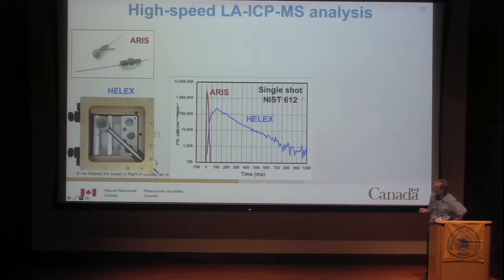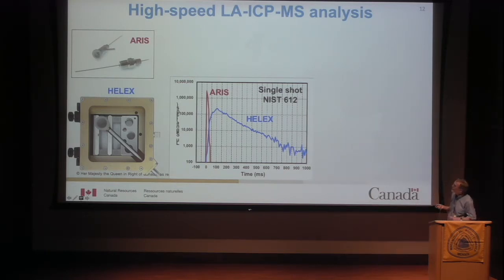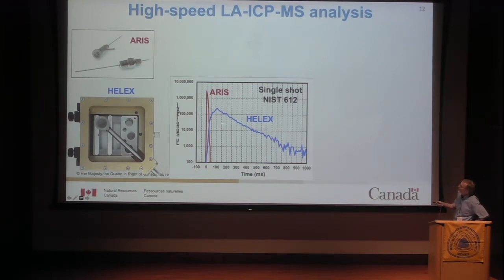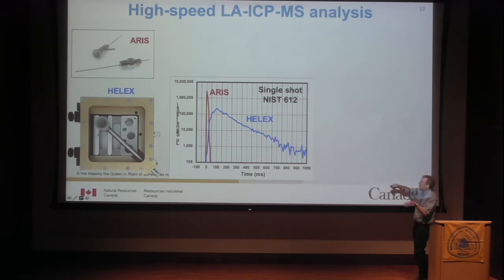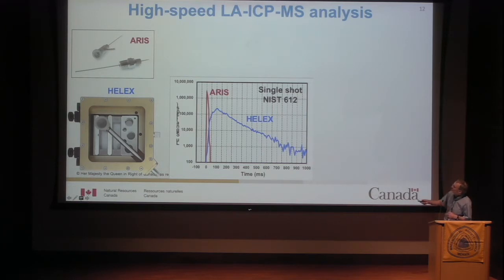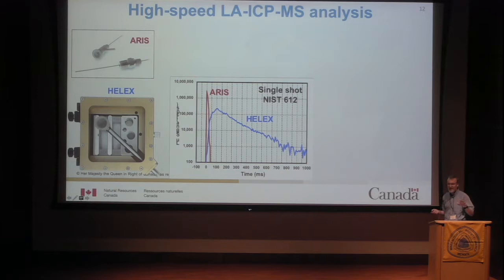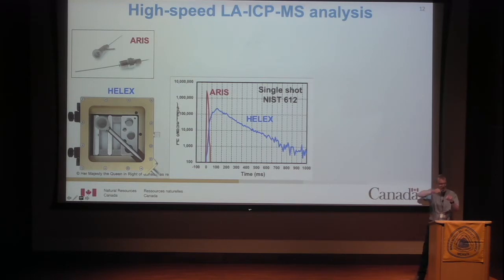Where I think the technique is really going is in speed. The big drive now seems to be to speed up this whole technology. A typical laser ablation cell signal from a single laser shot decays over about a second — so firing at 10 shots per second gives a roughly steady-state signal, ideal for slow sequential mass spectrometers. But recently, new sample introduction devices have been developed that flush cells in a matter of tens of milliseconds, which means you can now fire a laser at 50 shots per second and resolve every single peak.